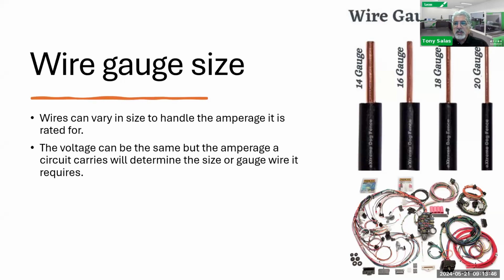And in this case, your gauge wire is too small, let's say 14 gauge, 12 gauge, or even 10 gauge, or even smaller than that. In other words, depending on the gauge size, if it's not going to carry that 110 amp peak, then you're finding out that it is underwired. So as we show you voltage drop testing, can the gauge of the wire cause the high resistance because it's underwired? And the answer is yes.